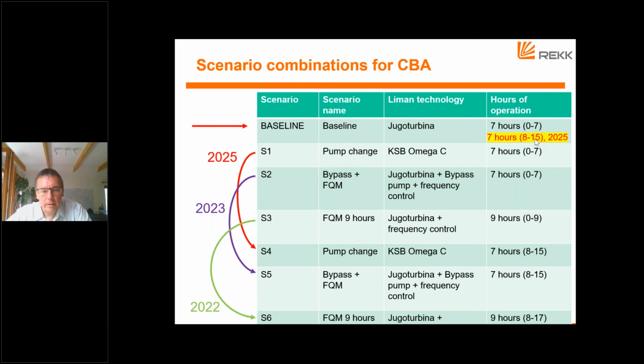We also had some hydraulic model runs in which the hours of operation were split. So some of the peak hours stayed in the night, some went to the daytime regime, but running these pumps at peak capacity twice a day means some problem for the network hydraulics. It can create pressure fluctuations, and that can result in breaking pipelines. So we eventually disposed of those scenarios, and we stick with the ones that you see on the screen.